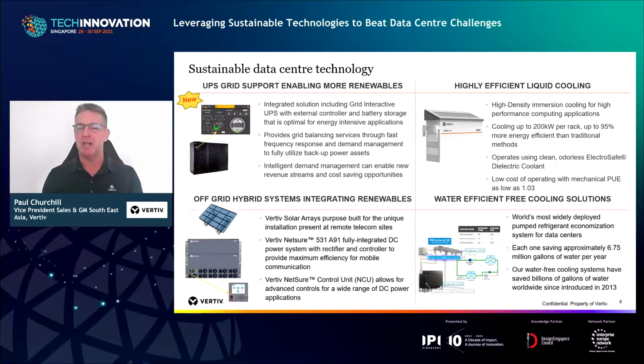That's starting to change now. As we try to reduce our footprint, become more efficient and more sustainable, you're starting to see a lot more computing power placed in one rack and one location. Immersion cooling, for example, can do up to 200 kilowatts, and it's a very efficient method with a PUE as low as 1.03. At this stage it's mainly used in supercomputing, the really high density applications, but Vertiv sees that extending into the data center space as time goes on.